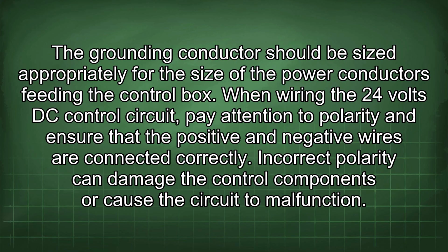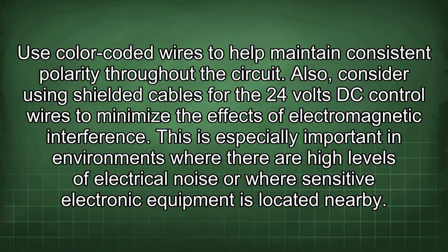When wiring the 24 volts DC control circuit, pay attention to polarity and ensure that the positive and negative wires are connected correctly. Incorrect polarity can damage the control components or cause the circuit to malfunction. Use color-coded wires to help maintain consistent polarity throughout the circuit.